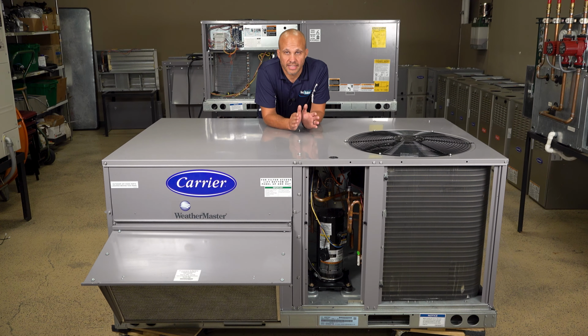So a gas-fired rooftop unit or an electric rooftop unit can be upgraded to a heat pump version. It looks the same. It's the same cabinet, same fans, same coils, same everything. We're literally just adding a reversing valve to those.